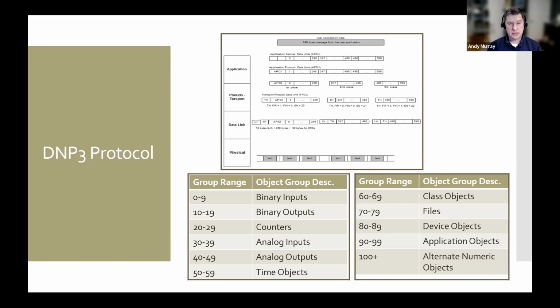It has these things called IIN bits, internal indication notifiers. One of them would be that the time needs to be synced, another may indicate I have some of these event data, and another can indicate if the field device comes offline. So if there's trouble out at the field device, that comes back built into the protocol, as opposed to having to create a separate data point saying this device is having issues.